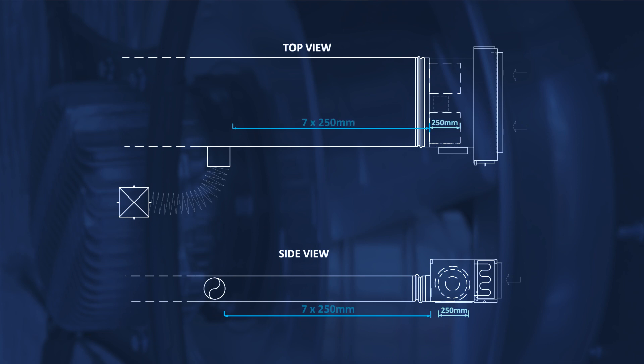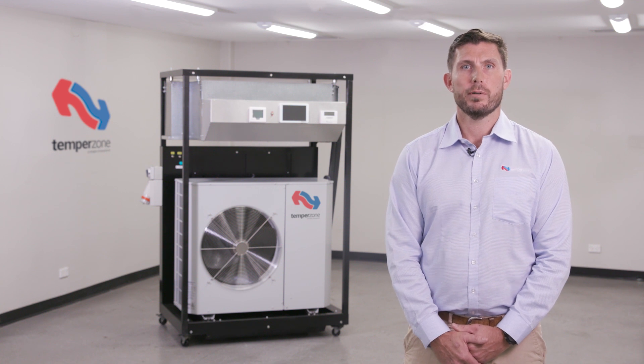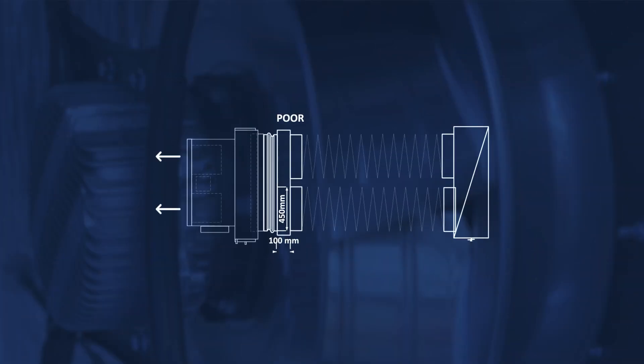As a general rule, supply air plenums should be seven times the length of the width of the fan barrel before the first takeoff spigot. This will allow space for turbulence to settle and static pressure to equalize for even air distribution. Units with high amounts of turbulence at the spigots suffer from high pressure losses and noise.